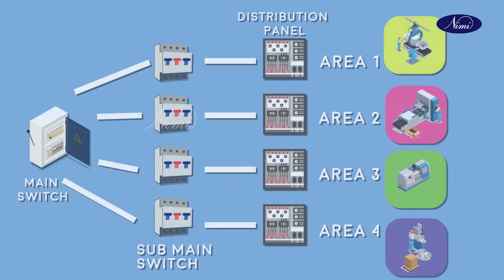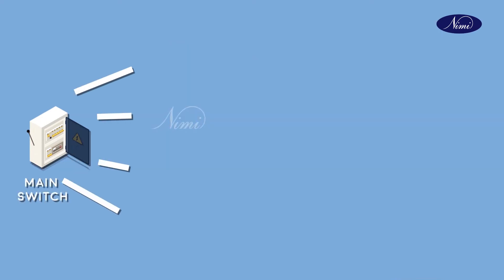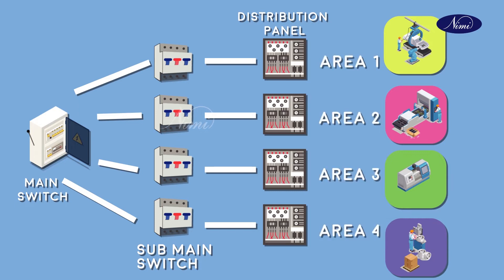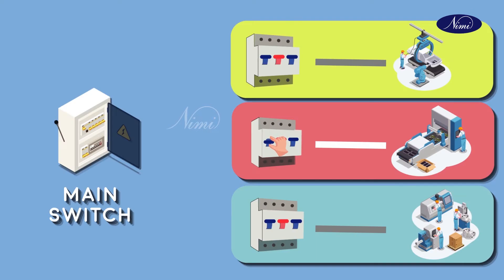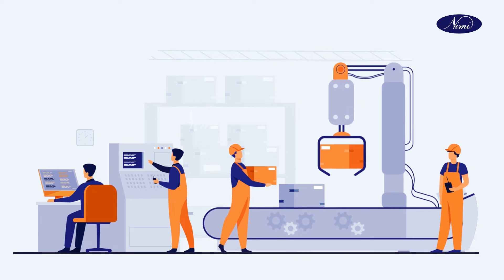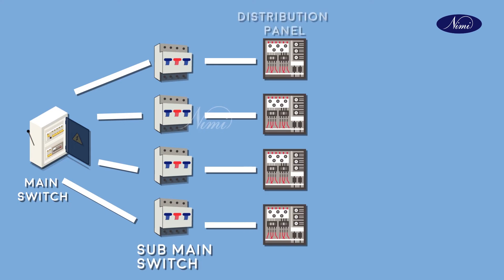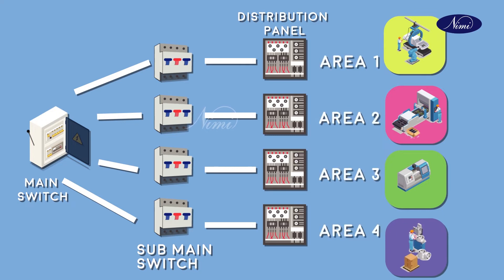This is a sample of a single line diagram of an electrical supply system in a workshop. In this there is a main switch and four sub-main switchers and their corresponding distribution board to control the electrical supply to a particular division. In case of any emergencies, the corresponding supply should be cut off without delay. In a well-organized workshop, the main switch, sub-main switchers and distribution boards will have clear marking to show their area of control.